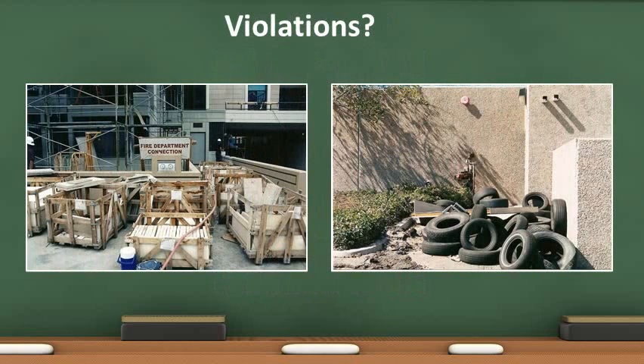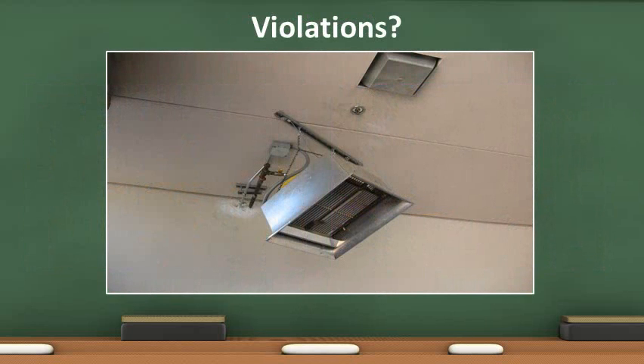Access to all fire protection equipment is required. Storage, vegetation, and anything obstructing the fire protection equipment is not permitted. Is this sprinkler head obstructed? Yes, it is. Sprinkler heads are required to be located away from anything that will obstruct the sprinkler pattern. In this photo, the proximity of the equipment to the sprinkler head will cause the sprinkler pattern to be disrupted.